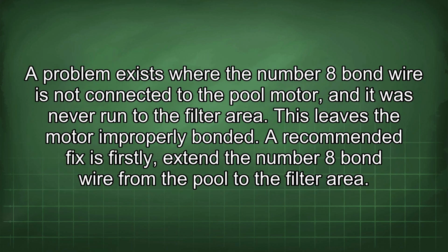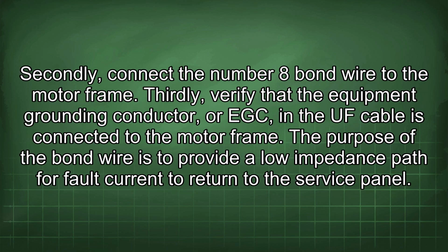pool. A problem exists where the number 8 bond wire is not connected to the pool motor and it was never run to the filter area. This leaves the motor improperly bonded. A recommended fix is firstly, extend the number 8 bond wire from the pool to the filter area. Secondly, connect the number 8 bond wire to the motor frame. Thirdly, verify that the equipment grounding conductor, or EGC, in the UF cable is connected to the motor frame.